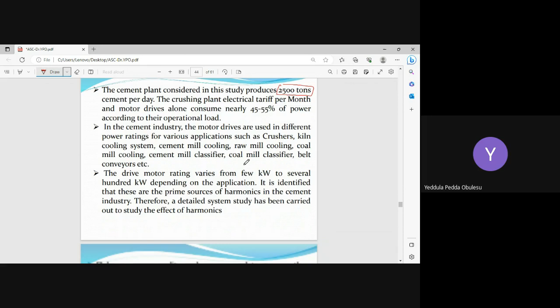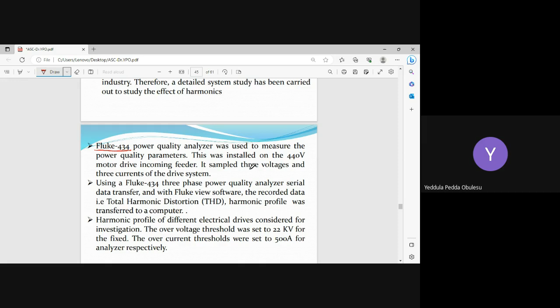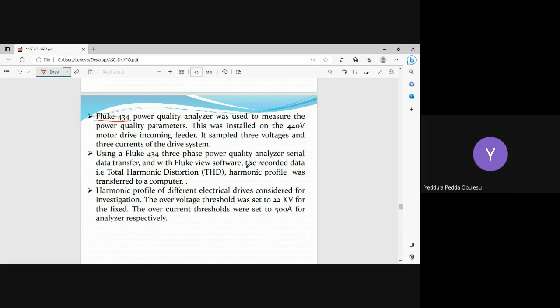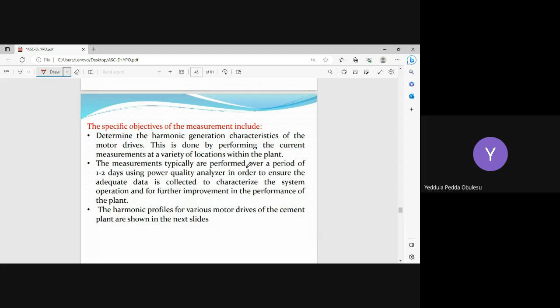To do this harmonic analysis, we used the Fluke 434 power quality analyzer. We connected it continuously for 2 days because we wanted to see the variation in the data, and we took the data for both voltages as well as currents. If you have experience with the Fluke 434 power quality analyzer, you will know that it also comes with software. The data we take with this instrument can be transferred to our laptop, where we can use all this harmonic profile.